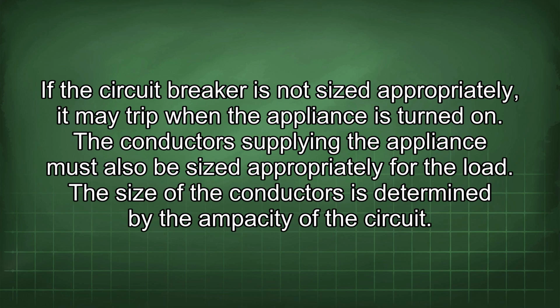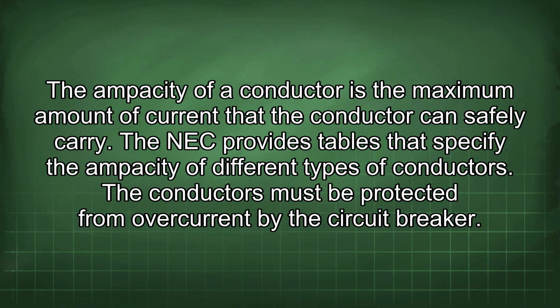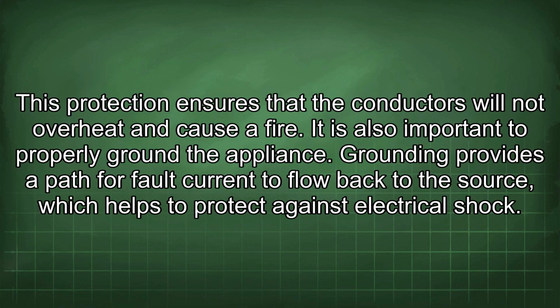The conductor supplying the appliance must also be sized appropriately for the load. The size of the conductors is determined by the ampacity of the circuit. The ampacity of a conductor is the maximum amount of current that the conductor can safely carry. The NEC provides tables that specify the ampacity of different types of conductors. The conductors must be protected from overcurrent by the circuit breaker. This protection ensures that the conductors will not overheat and cause a fire.